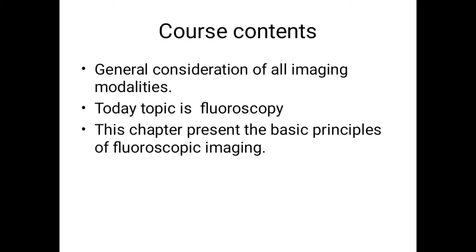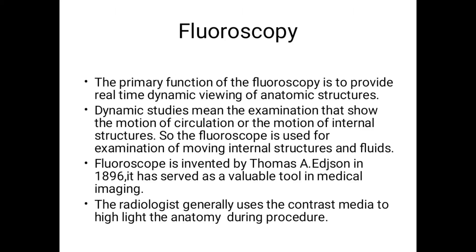What is fluoroscopy? The primary function of fluoroscopy is to provide real-time dynamic viewing of anatomic structures. With a simple X-ray, we take a spot film and then remove the patient. Fluoroscopy is more advanced — we continuously use X-ray to view moving structures in real time.